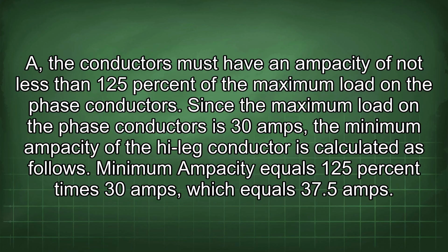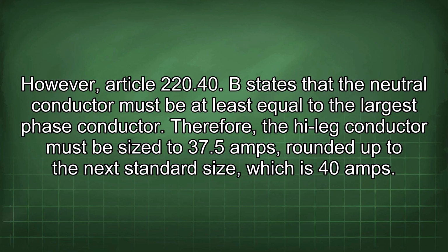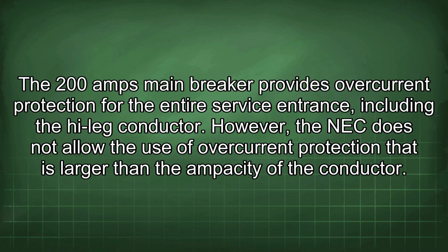Since the maximum load on the phase conductors is 30 amps, the minimum ampacity of the high leg conductor is calculated as follows. Minimum ampacity equals 125% times 30 amps, which equals 37.5 amps. However, Article 220.40 B states that the neutral conductor must be at least equal to the largest phase conductor. Therefore, the high leg conductor must be sized to 37.5 amps, rounded up to the next standard size, which is 40 amps. The 200 amps main breaker provides overcurrent protection for the entire service entrance, including the high leg conductor.